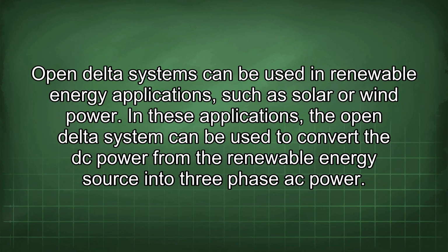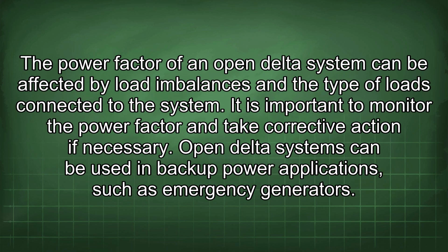Open delta systems can be used in renewable energy applications, such as solar or wind power. In these applications, the open delta system can be used to convert the DC power from the renewable energy source into three-phase AC power. The power factor of an open delta system can be affected by load imbalances and the type of loads connected to the system. It is important to monitor the power factor and take corrective action if necessary.